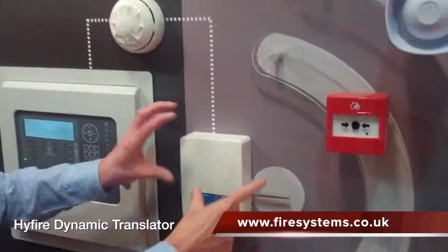Not only has the amount of wireless fire alarm devices increased from 32 to a much larger capacity of 127, but the module is also dynamic. You may be asking the question, what is a dynamic translator? The dynamic feature of the module allows the radio signal to have more than one pathway back to the base station. Therefore, if the radio signal's path is blocked for whatever reason, the dynamic feature of the translator will reroute the radio signal back via an alternative route.